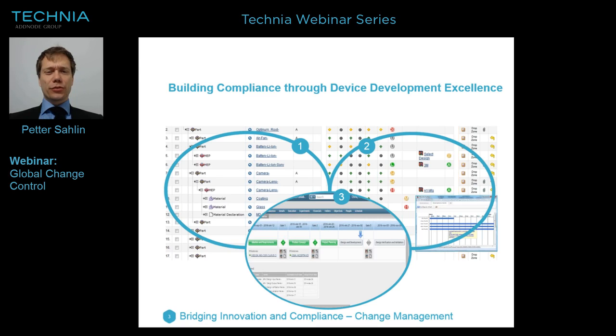Today's main focus is on item number one, which is the product definition, where we review the breakdown of the regulatory product. It has relevance because the BoM is also the foundation for the DMR, and typically it's the DMR which we refer to in our concessions or our NCRs. So everything is interlinked and connected.